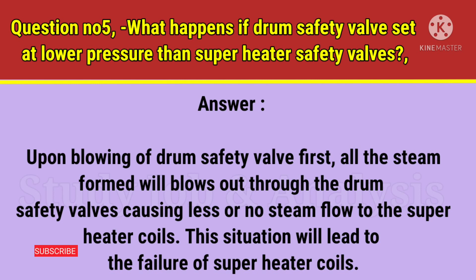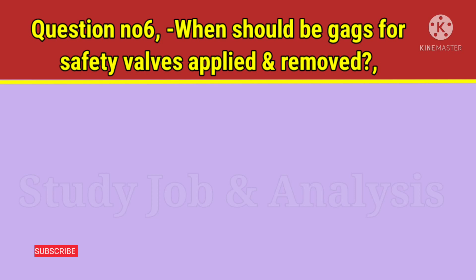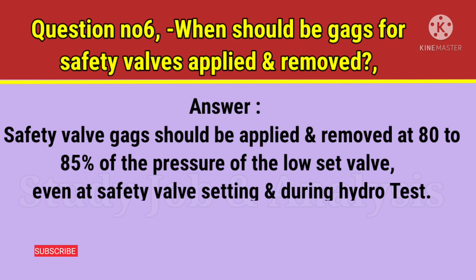Question number 6: When should gags for safety valves be applied and removed? Answer: Safety valve gags should be applied and removed at 80-85% of the pressure of the low-set valve, even at safety valve setting and during hydro test.